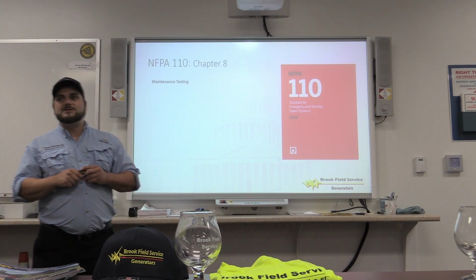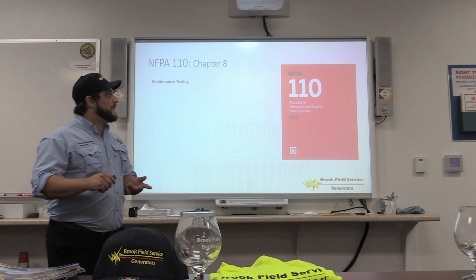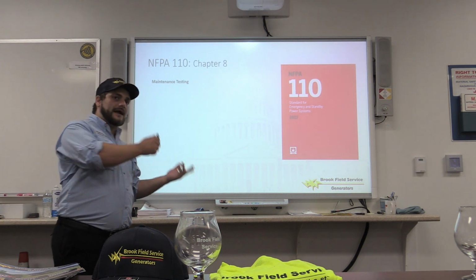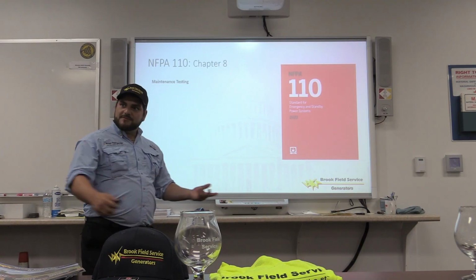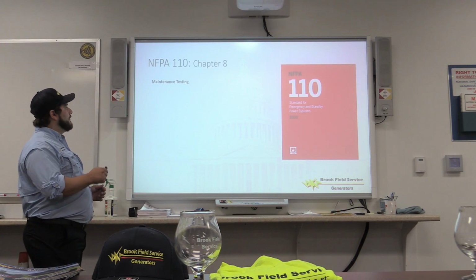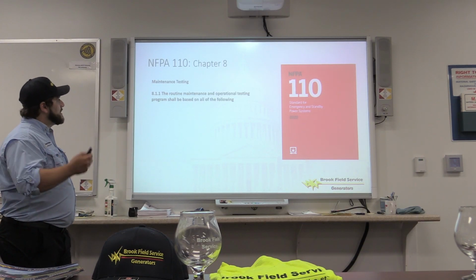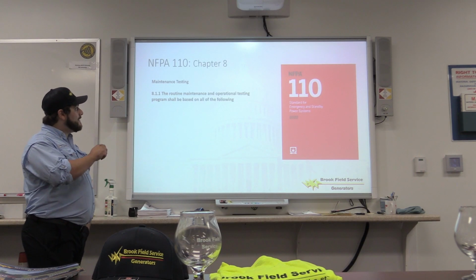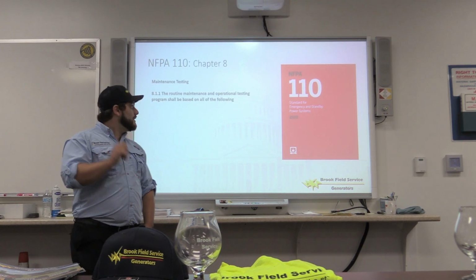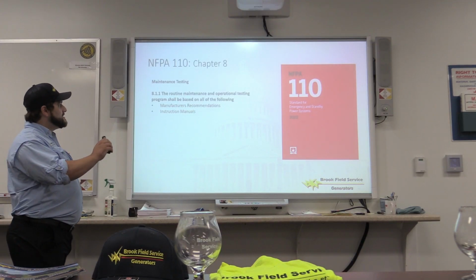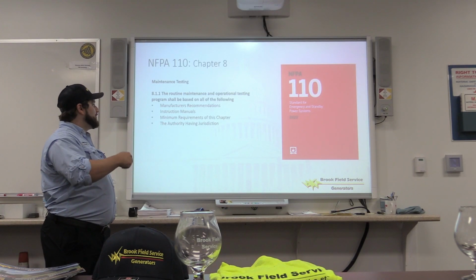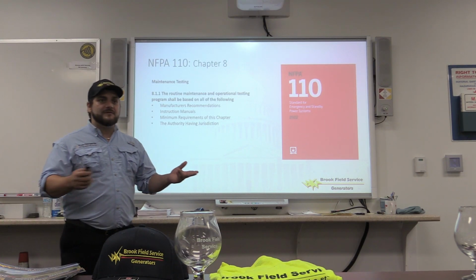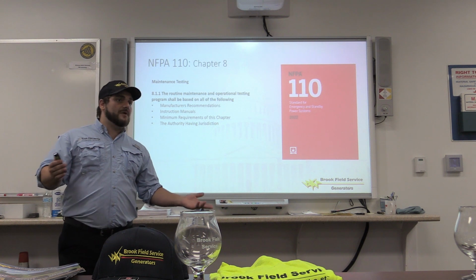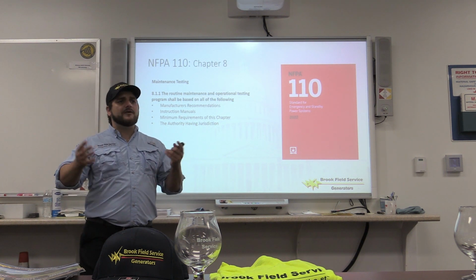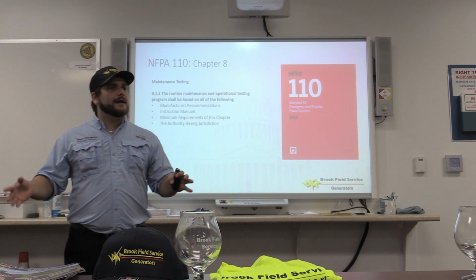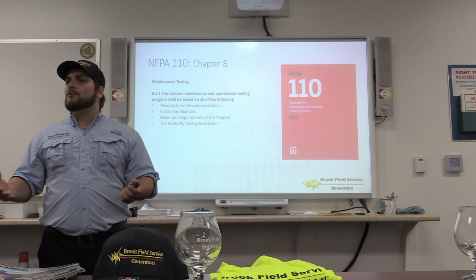Maintenance testing. Chapter 8 is the soup and nuts of NFPA 110. Again, you can have an entire course on NFPA 110 and some of the other national electric codes, but when it comes to generator maintenance, this is the all-encompassing power. Section 1 says a routine maintenance and operational testing program shall, which in legalese means will, be based on the following: manufacturer recommendations, instruction manuals, minimum requirements of this chapter, and the authority having jurisdiction. So what you will see based on NFPA 110 is the minimum of what you should expect. I hear many times that a lot of guys have their own folks maintain things, which is okay, but when we get into this, you will realize that having your own maintenance crew handle these things is just not enough.